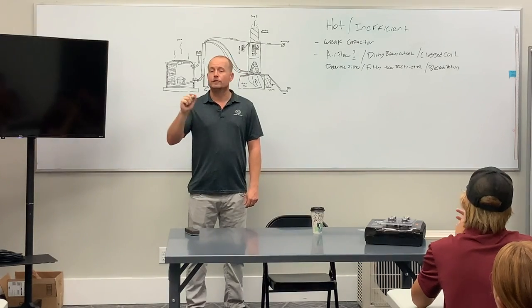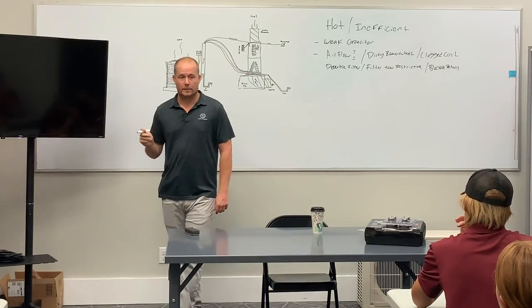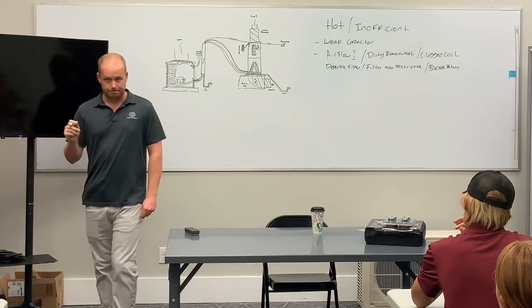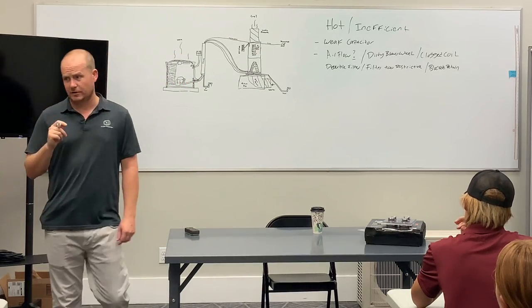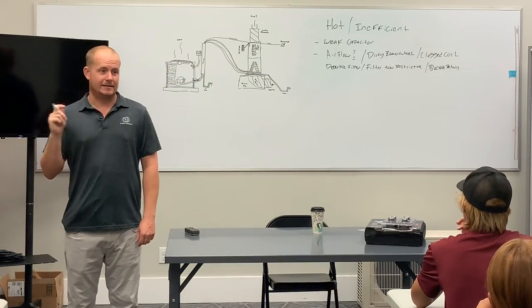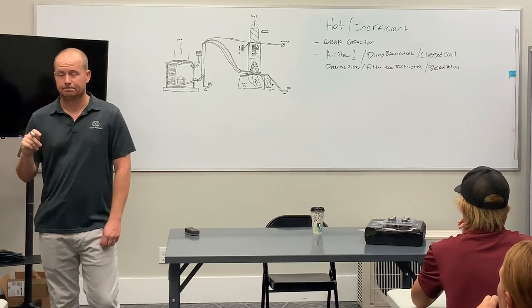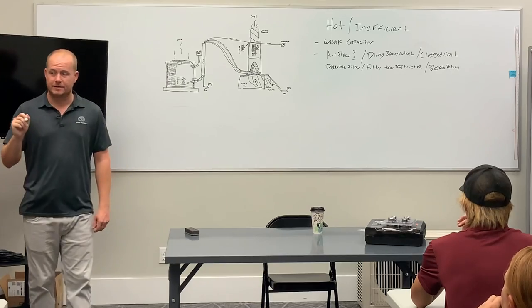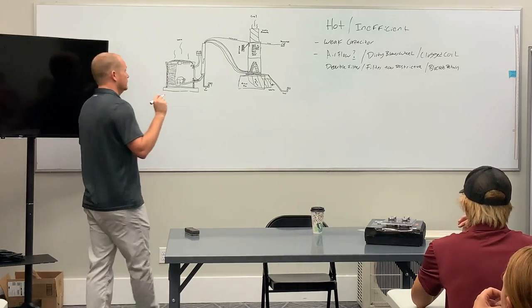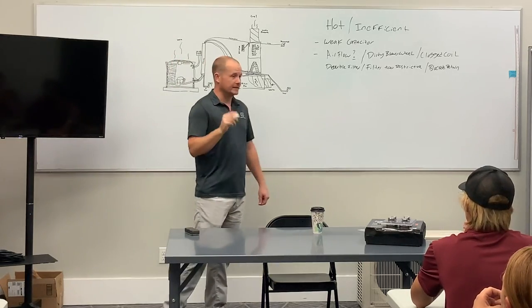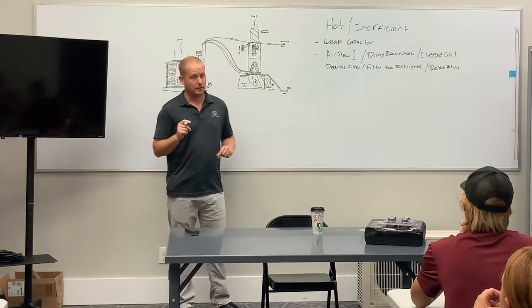So, those of you doing installs or working on newer equipment that has ECM motors in it, of which most of what we install nowadays, if not all, has ECM blowers, either X13 or true variable, in those applications you're going to see a motor get inefficient with low airflow.